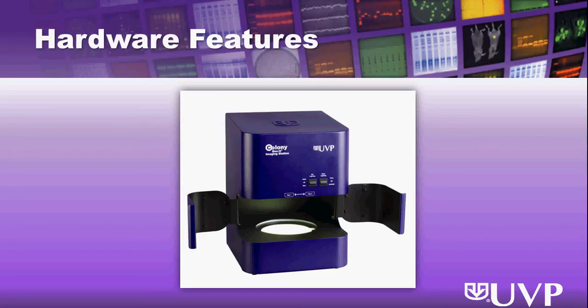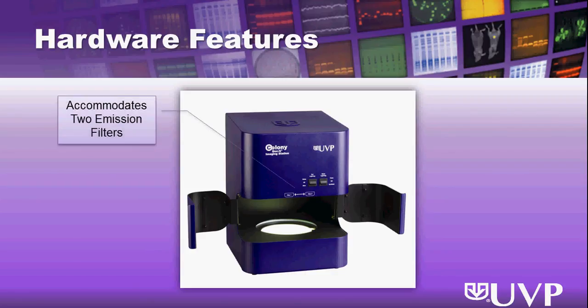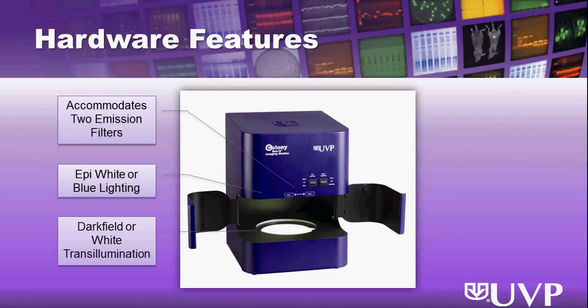Moving on to a hardware features overview, you can see an image of the ColonyDoc-It imaging station with its darkroom doors open. The system is capable of accommodating two emission filters, which are useful for imaging colonies that express at a certain wavelength, such as GFP colonies. The system integrates epi white and blue lighting, as well as dark field or white transillumination, all of which are controllable using the two black switches located on the front of the system.